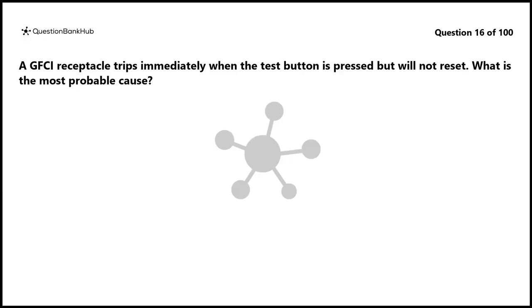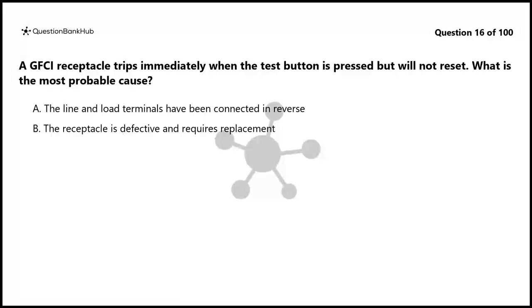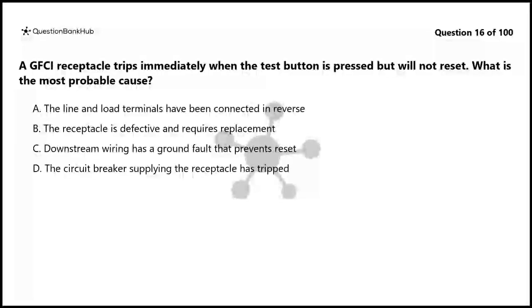Question 16. A GFCI receptacle trips immediately when the test button is pressed but will not reset. What is the most probable cause? A. The line and load terminals have been connected in reverse. B. The receptacle is defective and requires replacement. C. Downstream wiring has a ground fault that prevents reset. D. The circuit breaker supplying the receptacle has tripped.